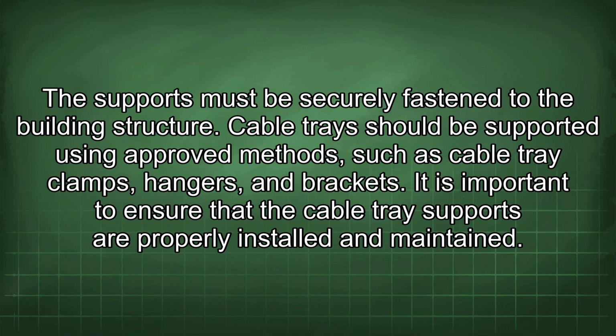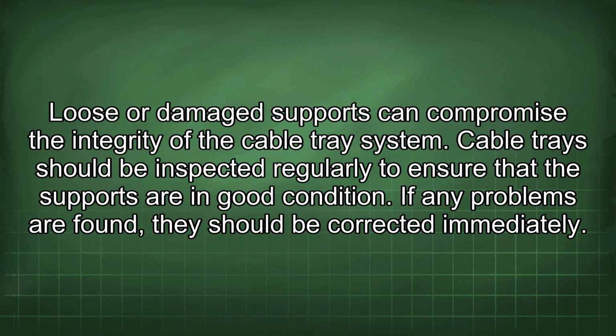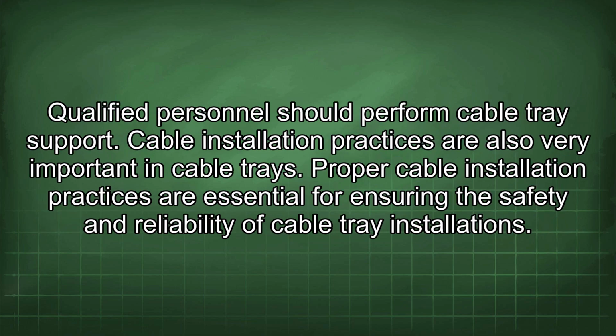It is important to ensure that the cable tray supports are properly installed and maintained. Loose or damaged supports can compromise the integrity of the cable tray system. Cable trays should be inspected regularly to ensure that the supports are in good condition. If any problems are found, they should be corrected immediately. Qualified personnel should perform cable tray support. Cable installation practices are also very important in cable trays.